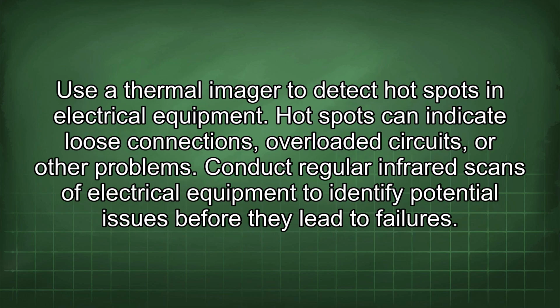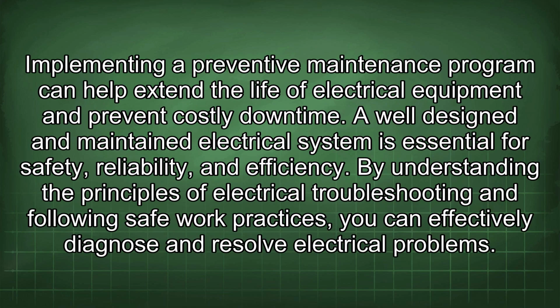Use a thermal imager to detect hot spots in electrical equipment. Hotspots can indicate loose connections, overloaded circuits, or other problems. Conduct regular infrared scans of electrical equipment to identify potential issues before they lead to failures. Implementing a preventive maintenance program can help extend the life of electrical equipment and prevent costly downtime.